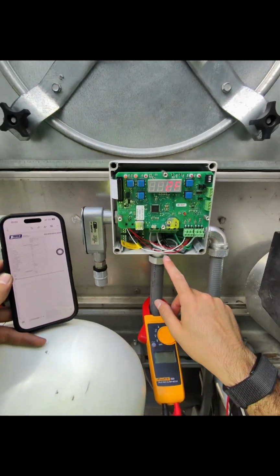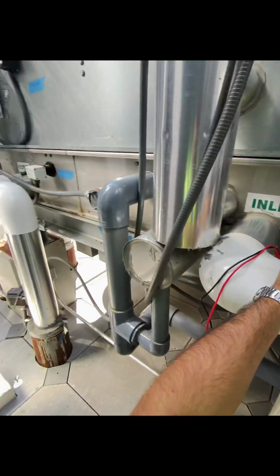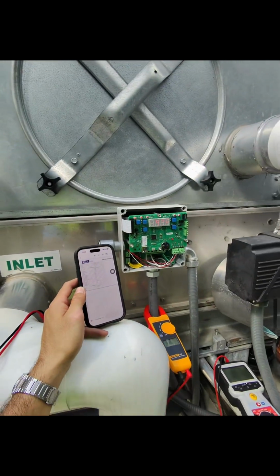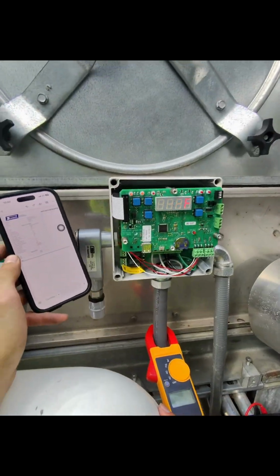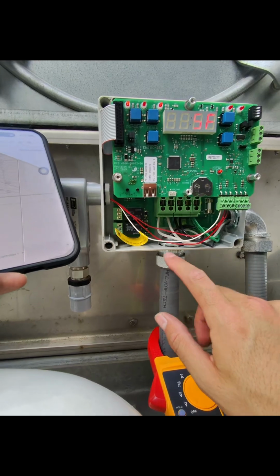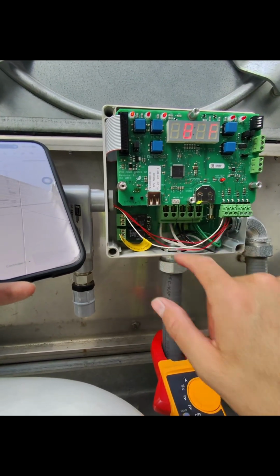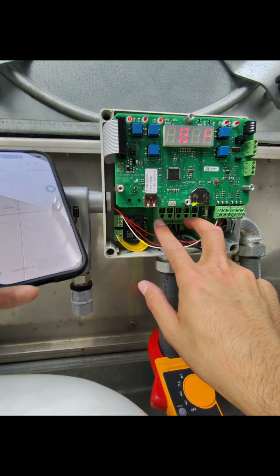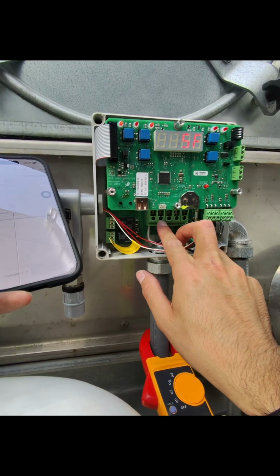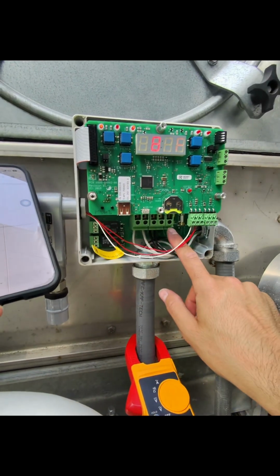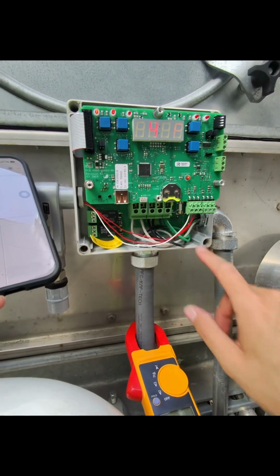I already did my Megger test here. We had some low Meggers on some of the power kits here, so we had to go through and fix those. You can see the heater wiring, so you have your power coming in, AC in negative, AC in positive on these 2 terminals, and then your heat trace going out are on the middle terminals here, and your earth or your ground is the rightmost terminal.